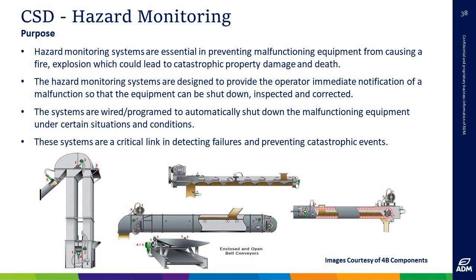However, when you have them in place, they need to be checked. I know yesterday there was talk about 6-month checks. We do quarterly checks, visual, for things like placement. We do 6-month speed testing. I'm not telling you to do this, but we do 6-month speed function testing, and we do annual freeze spray to check and make sure the display is correct, that the correct bearing is displaying on the HMI correctly and whatnot.